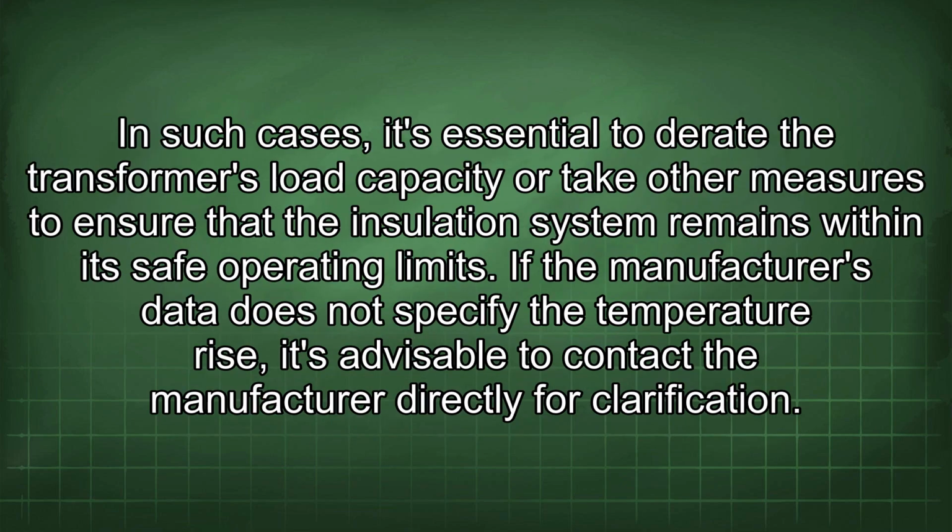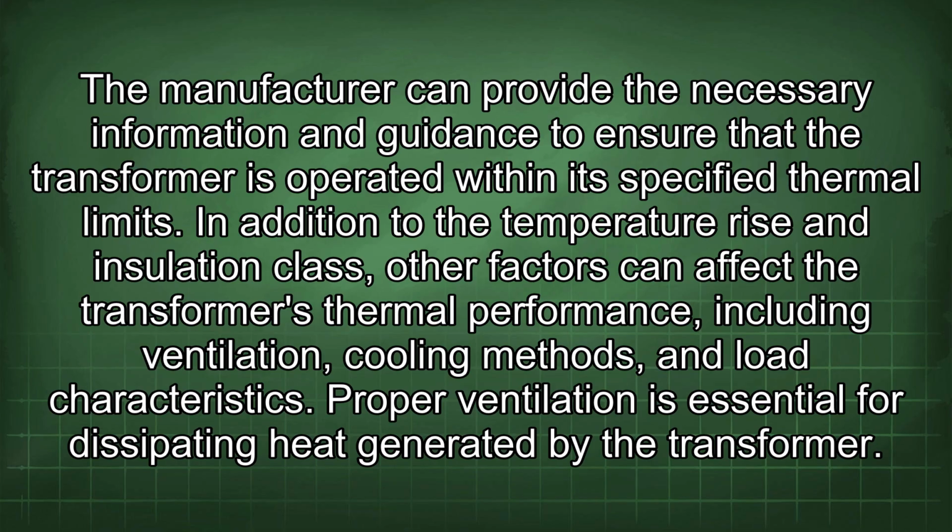In such cases, it's essential to derate the transformer's load capacity or take other measures to ensure that the insulation system remains within its safe operating limits. If the manufacturer's data does not specify the temperature rise, it's advisable to contact the manufacturer directly for clarification.